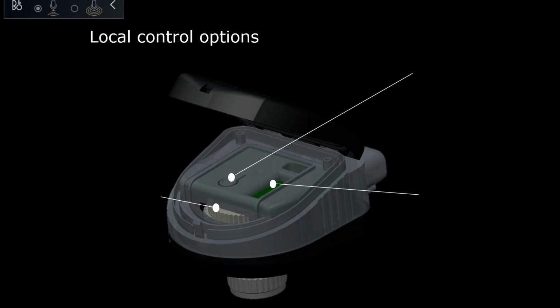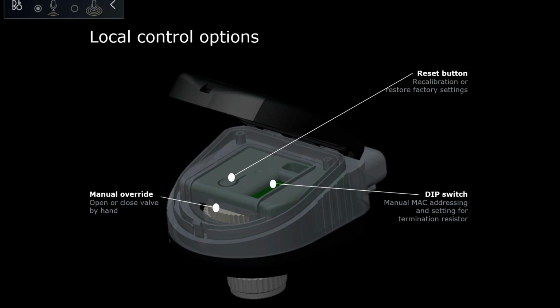Local control options. You have the reset, the manual override, and the dip switch. The manual override is just to move the actuator when power is off. The reset button is in case you need to recalibrate, or in case you are changing the communication protocol from Modbus RTU to BACnet and vice versa.